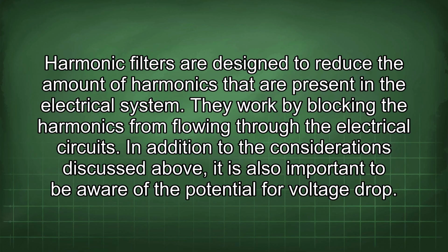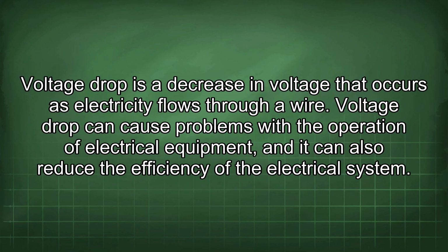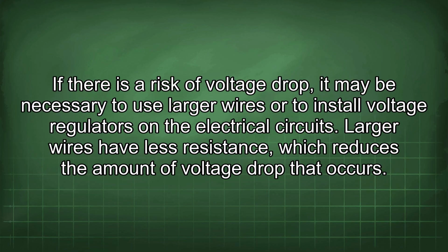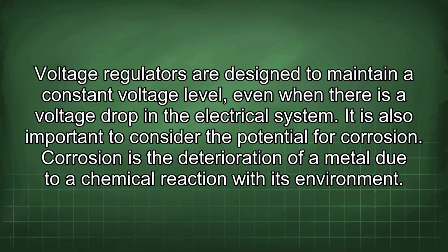In addition to the considerations discussed above, it is also important to be aware of the potential for voltage drop. Voltage drop is a decrease in voltage that occurs as electricity flows through a wire. Voltage drop can cause problems with the operation of electrical equipment, and it can also reduce the efficiency of the electrical system. If there is a risk of voltage drop, it may be necessary to use larger wires or to install voltage regulators in the electrical circuits. Larger wires have less resistance, which reduces the amount of voltage drop that occurs.